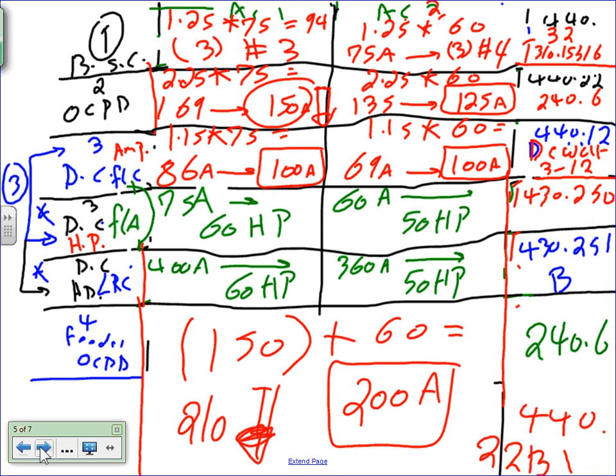Okay. Any comments, any questions? Similar to the motors. Now, you have to size this. Okay, can I go back? Remember when we talked about the overcurrent protection device right here? Number 2 is actually called the maximum overcurrent protection provided by the manufacturer. Number 1 and number 2 are almost always provided by the manufacturer. This is called minimum circuit ampacity, and this is maximum overcurrent protection. These two, the first and the second, are provided by manufacturers. If they are not, this is how we do it.